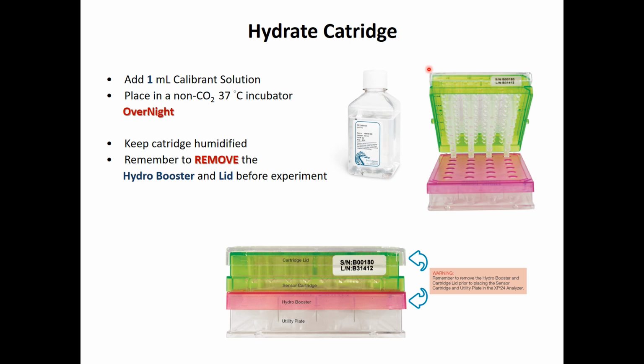Okay, and you can see here is a standard cartridge you will see with the XFe96 analyzer. It is composed of different parts. The bottom part is a utility plate, which is almost the same as a cell culture plate, but it is marked as utility plate. It is for calibration buffer, not for cell culture. Then the upper part is a hydro booster. It helps make sure the fluorescence probe is mixed well with the calibration solution and the air. Then here is the green one, the sensor cartridge, which incorporates the auto drug injection ports. And finally there is a lid to prevent dust.